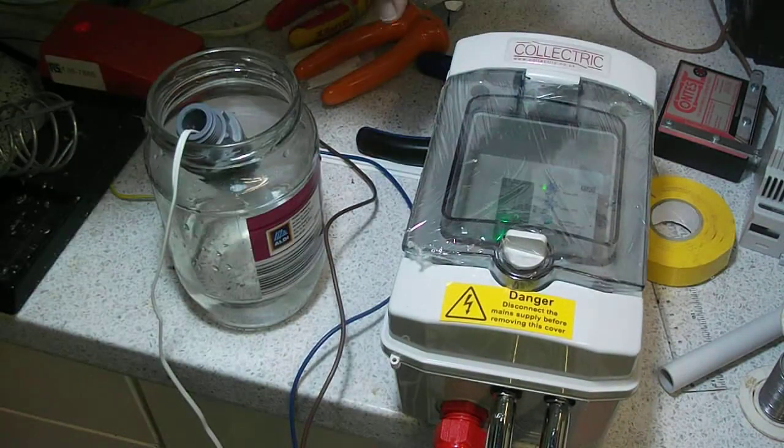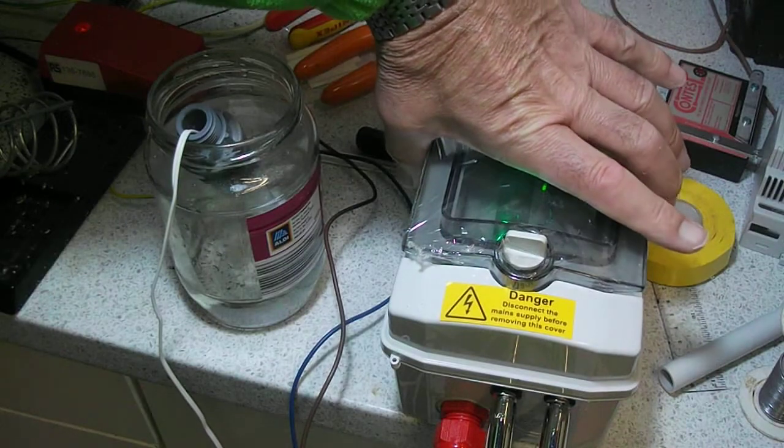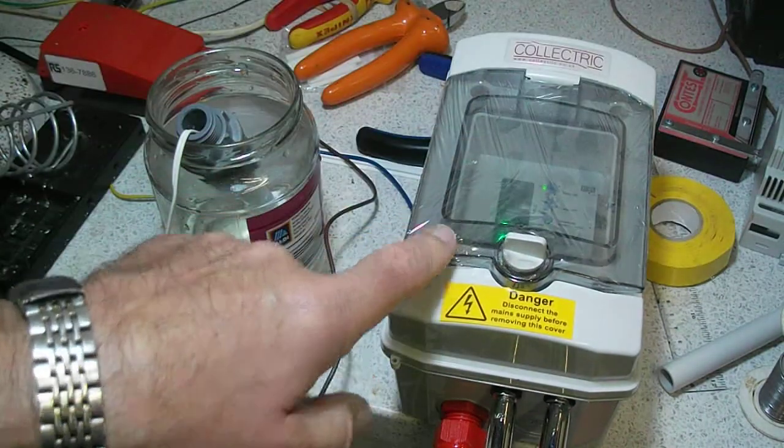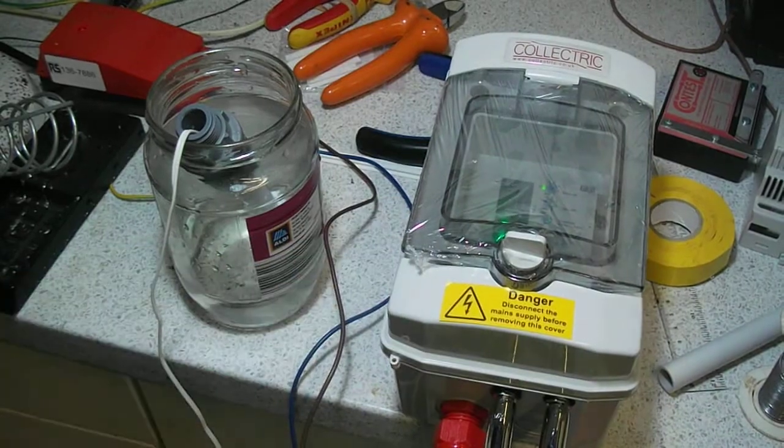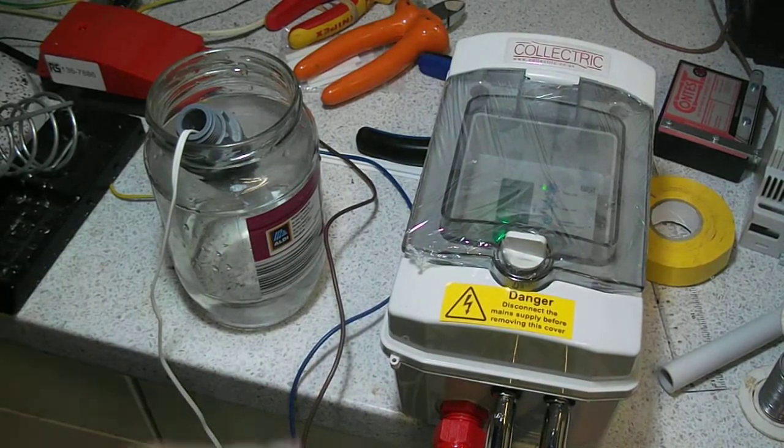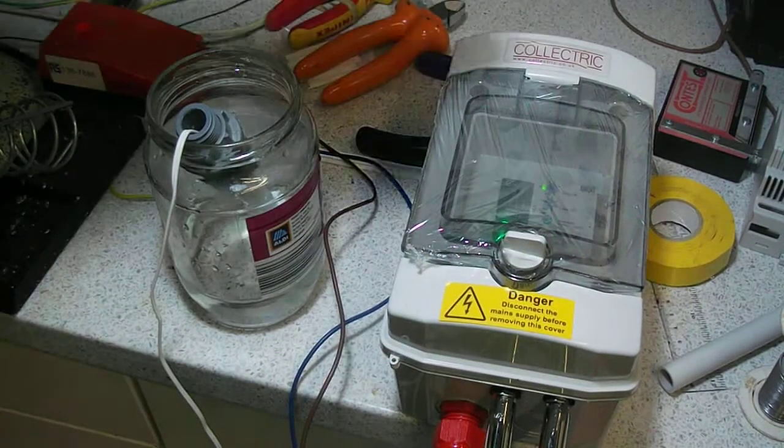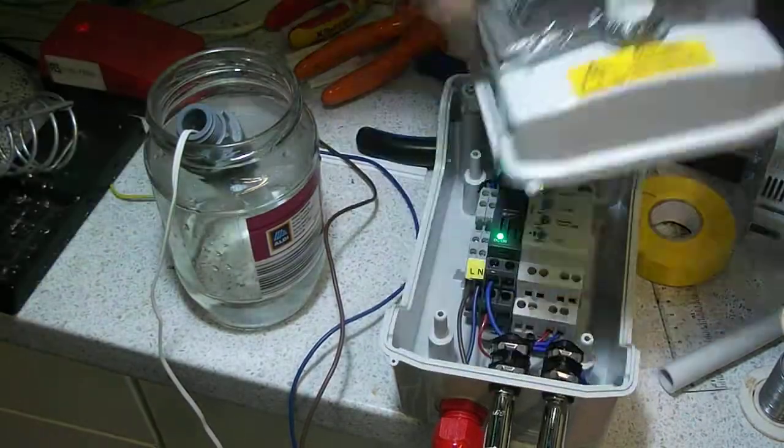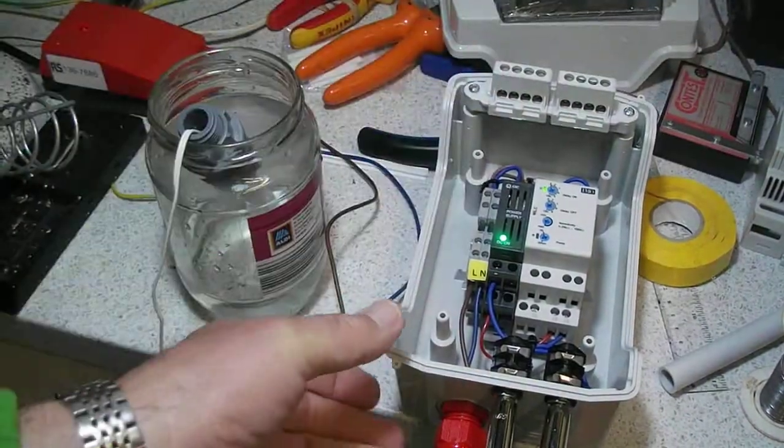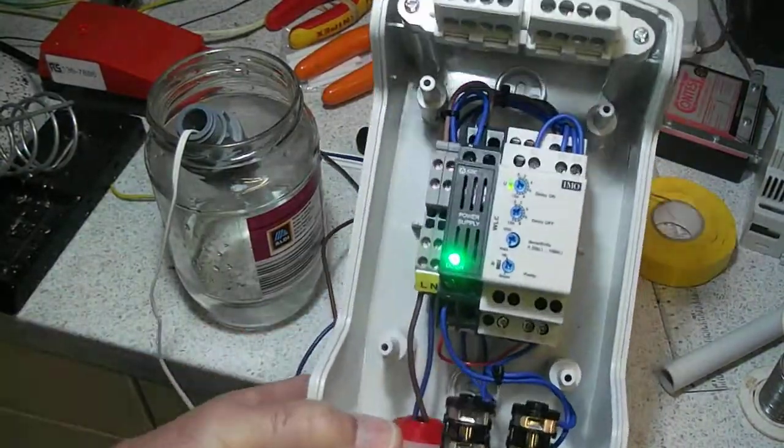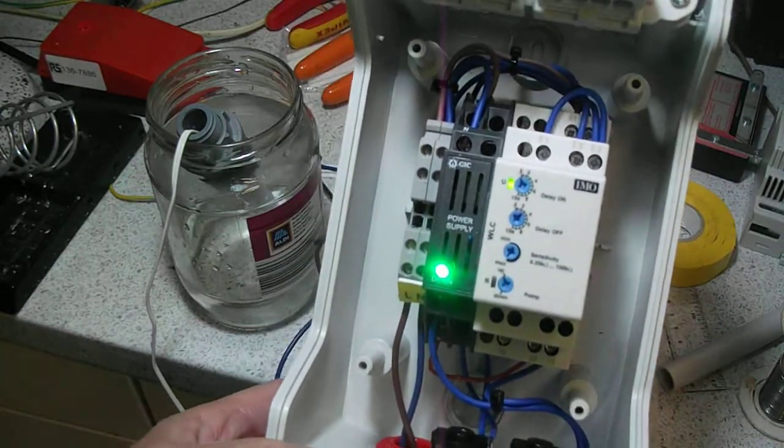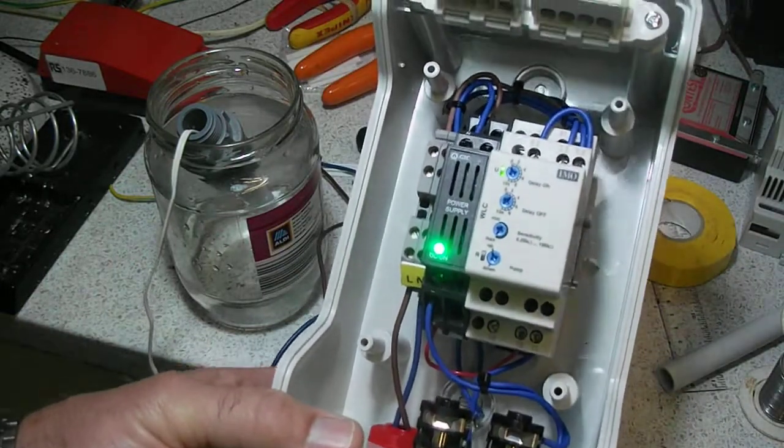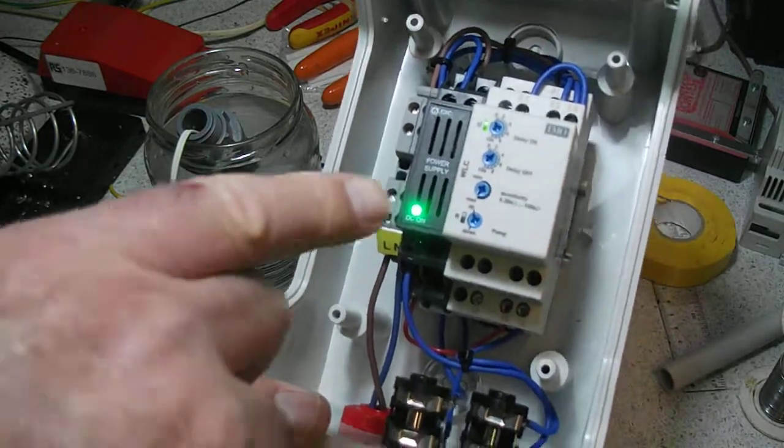This is quite useful because it's IP65, so it can be mounted outside. Take the lid off - inside we've got the IMO level controller, and we've set this so that it's pumping in the pump up position and set it to a few seconds delay in the off position.